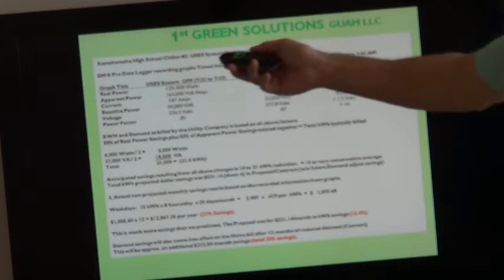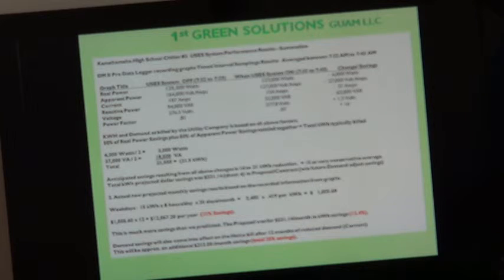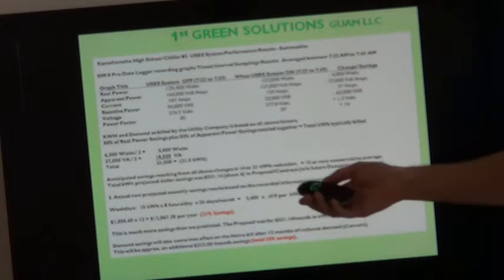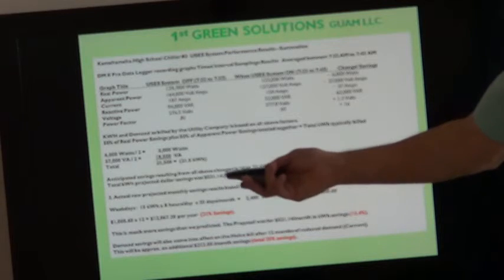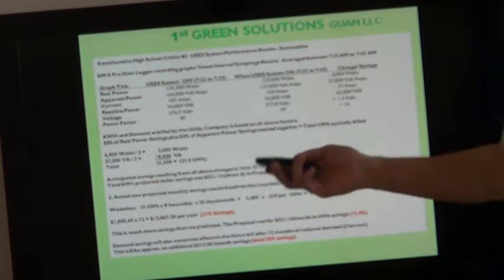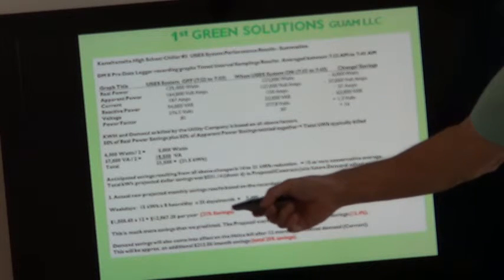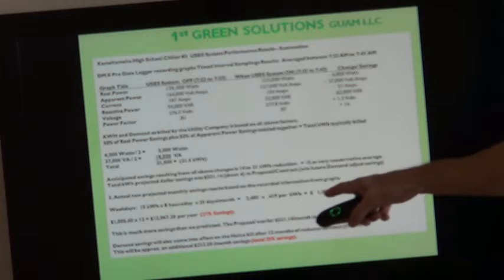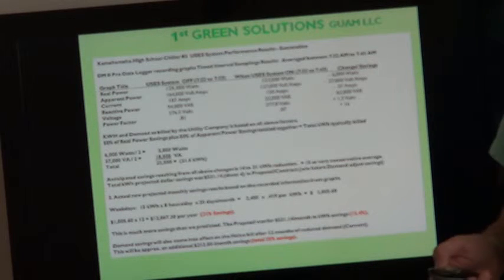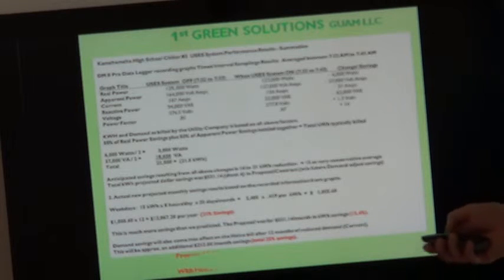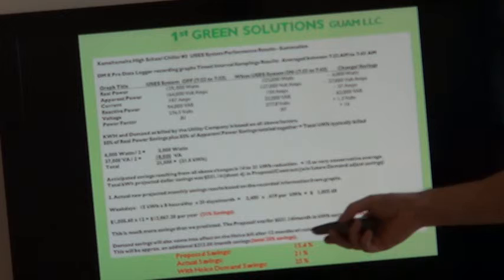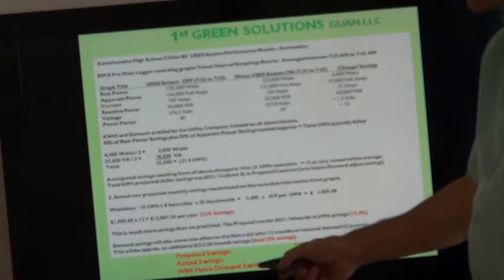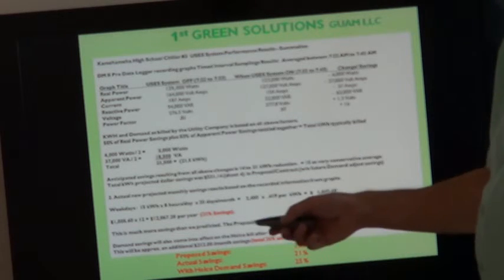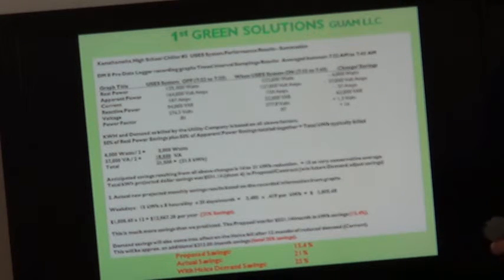The summation on this particular installation was also exceeding the proposed amount we projected would be saved by those 3 usage units. We had projected the savings would be $531 per month, and it ends up that from the recordings and the power bills that they're receiving, we are saving them $1,500 a month, almost double what we had projected. They will also be saving an additional demand savings, which Helco, the power company there in Hawaii, provides for them after 1 year of reduced demand.